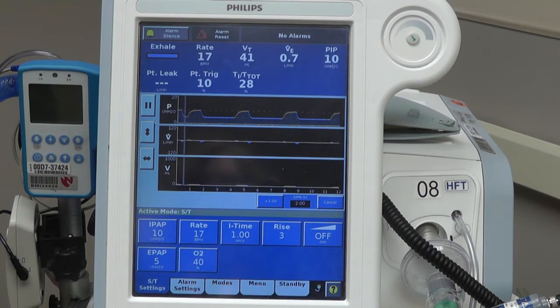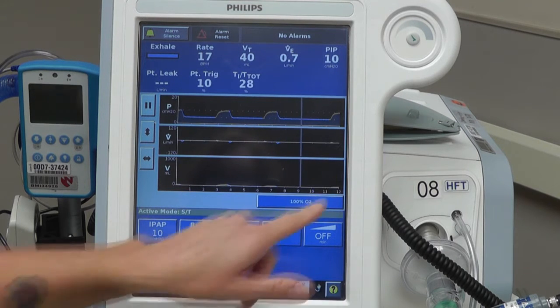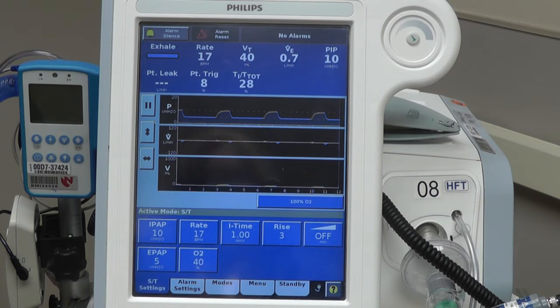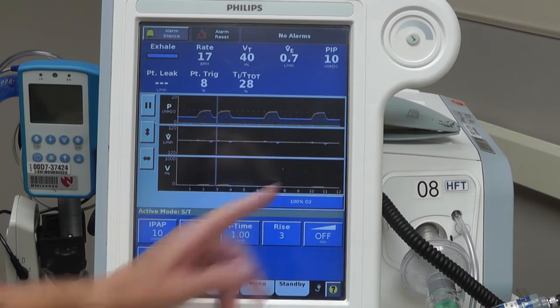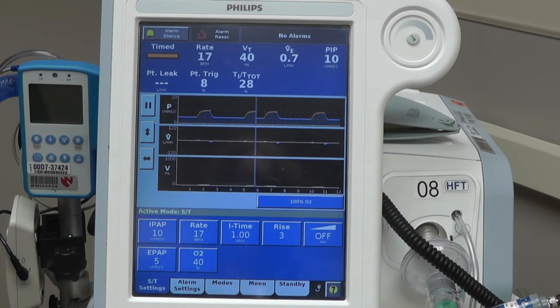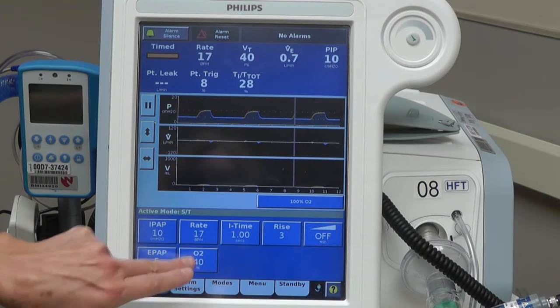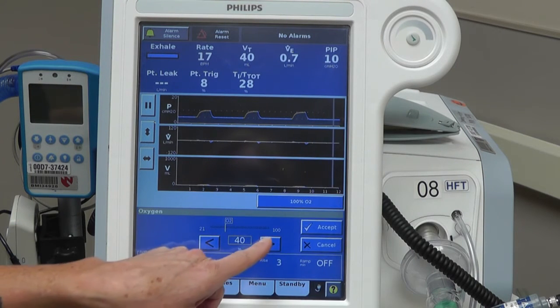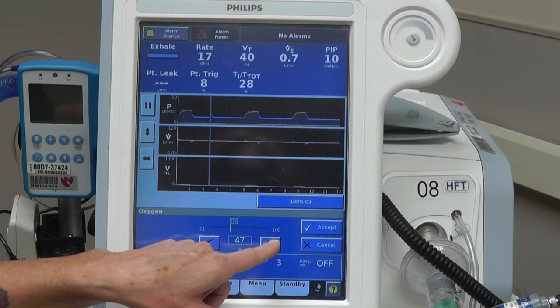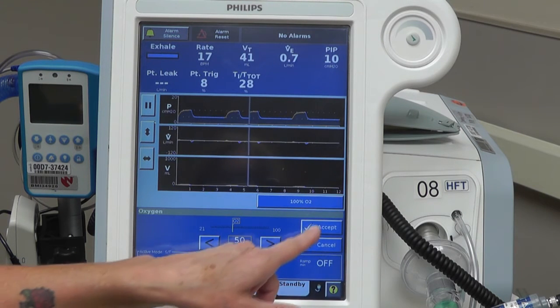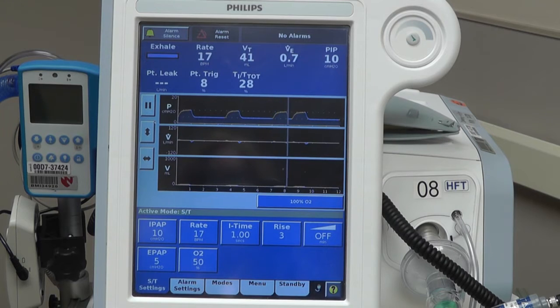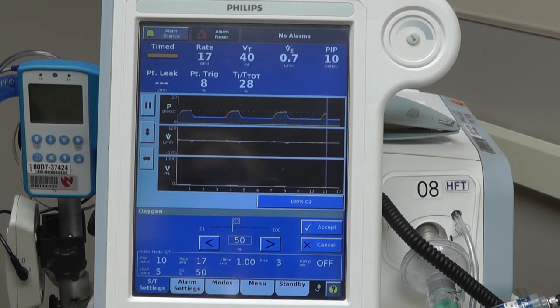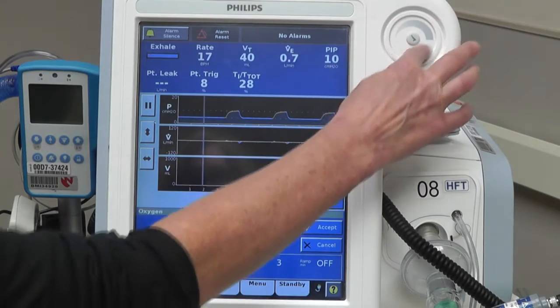There's a 100% O2 boost button. And when I push that, I have a 2-minute timer that immediately pops up, and we go to 100% for 2 minutes. I can cancel that at any time and go back to the FiO2 that we have set. An easy way to increase oxygen on your patient, if you need to increase anything other than 100%, you can hit the oxygen button here and increase the amount of oxygen delivered to your patient. But then you also have to hit the accept button.